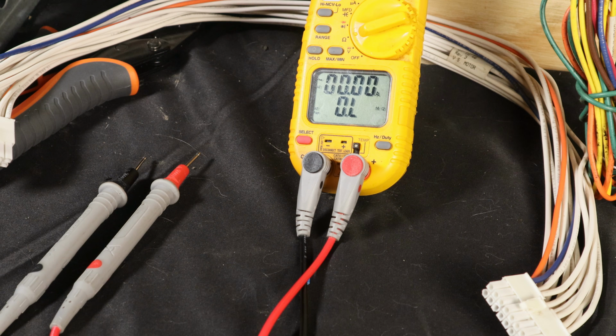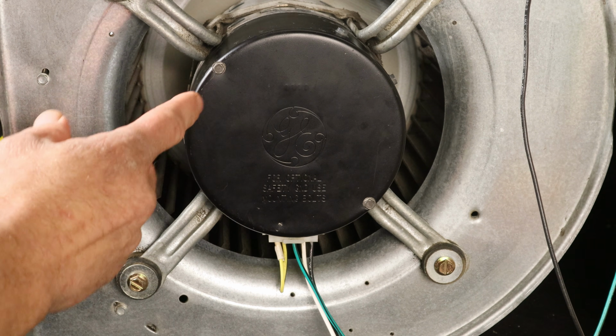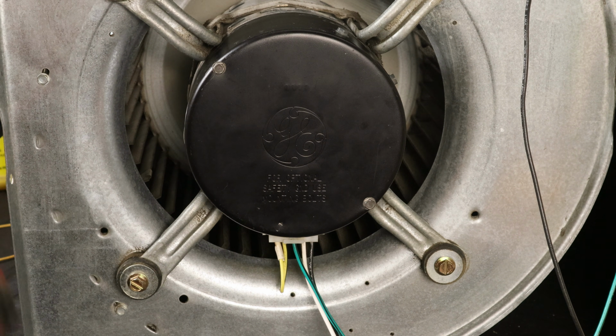But if your motor's still not starting, now it's time to actually dive in the motor. And the reason why I wait this long to do it, because it's not always easy to get into those things when they're actually inside the unit. So I try to save that for last. So to open up the motor, we have 2 bolts here holding it in. We're just going to take those out.